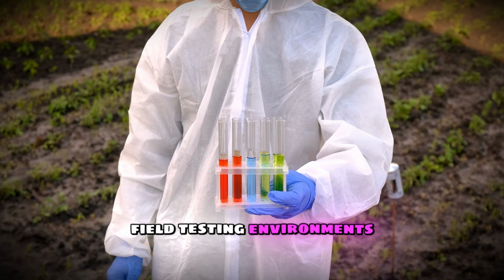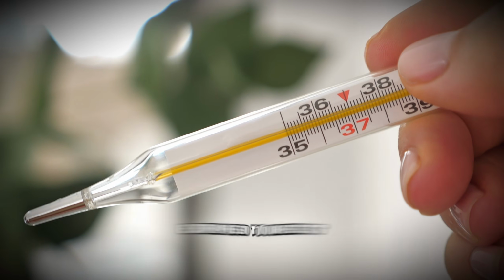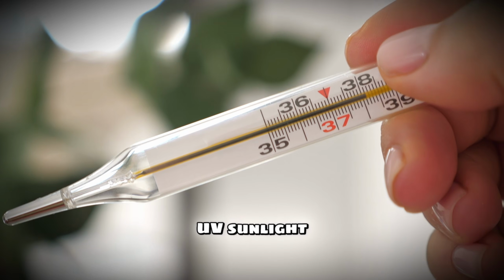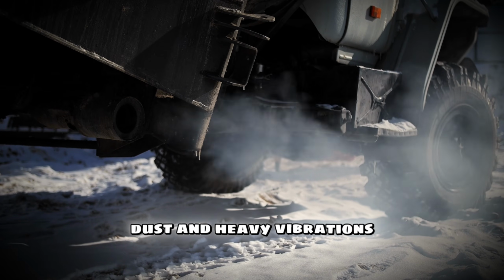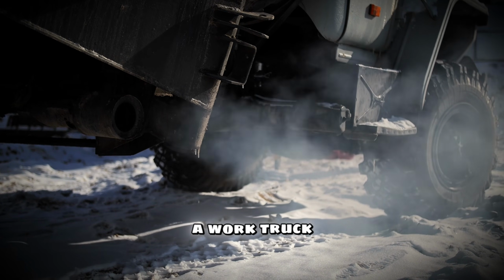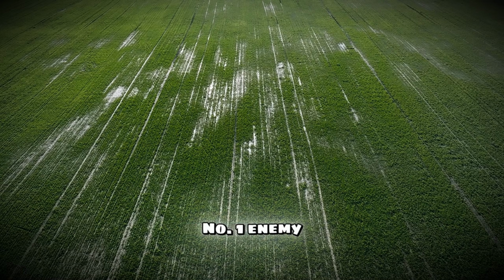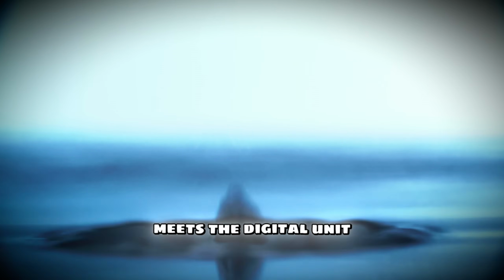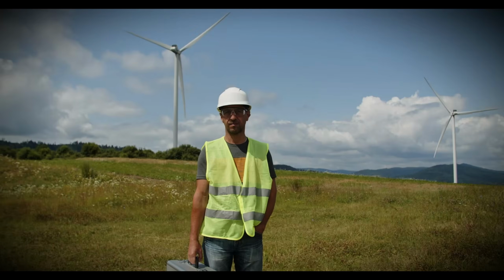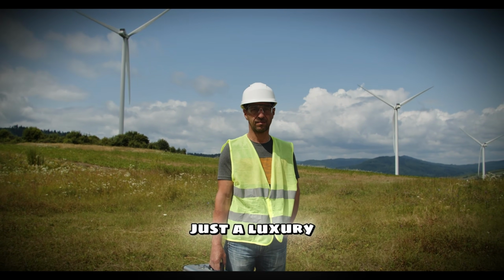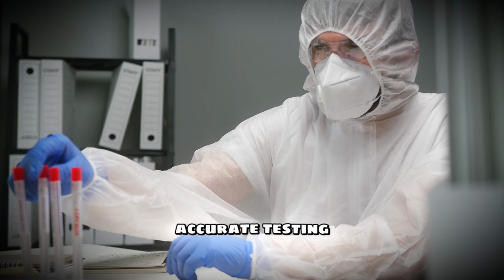Out in the field, it is a completely different story. Field testing environments are brutal. Your thermometer is exposed to direct UV sunlight, freezing winds, rain, dust, and heavy vibrations from sitting in the back of a work truck. Moisture is the #1 enemy in the field. If water gets into the connection point where the probe meets the digital unit, it can short the connection or create a false reading. This is why having equipment specifically rated for your environment is not just a luxury, it is a strict requirement for accurate testing.